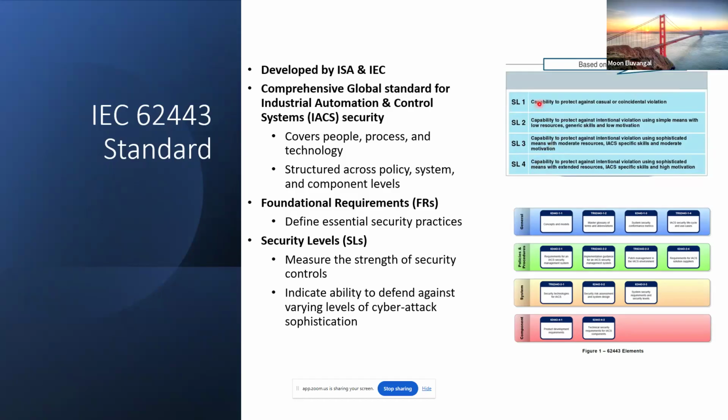So there is a standard, 62443-3-2, particularly this one. In this standard, there is a very detailed approach on how to perform a risk assessment for your plant. It talks about two different levels of risk assessment. One they call a high level risk assessment, and then there is a detailed risk assessment. The high level risk assessment identifies the zones and conduits in your plant.